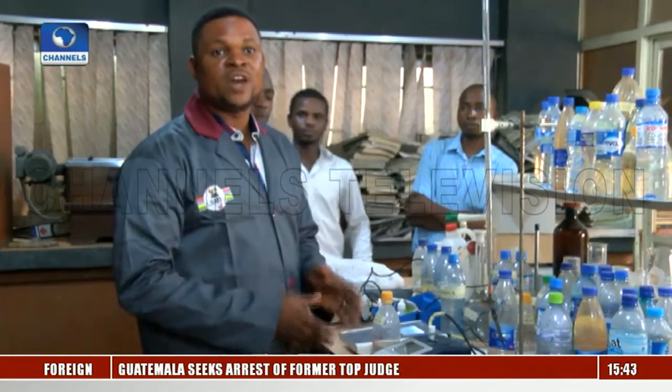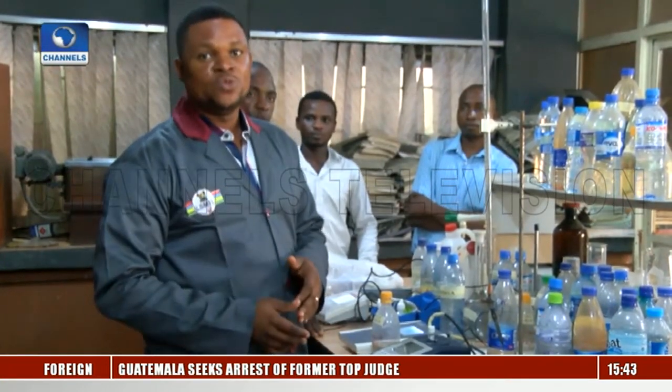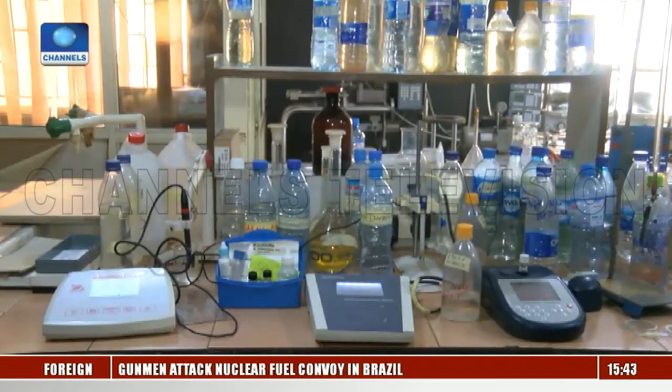The standard we use here is 5 NTU. NTU is nephelometric turbidity unit. So if the water sample is having less than 5, that means it's a pass. Then it has passed the turbidity parameter. Then samples of water already tested are displayed.